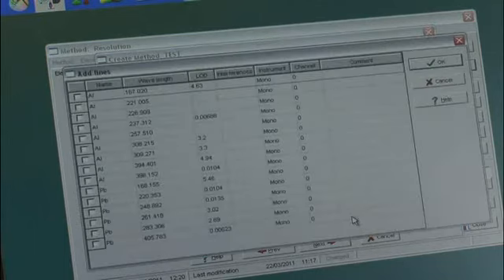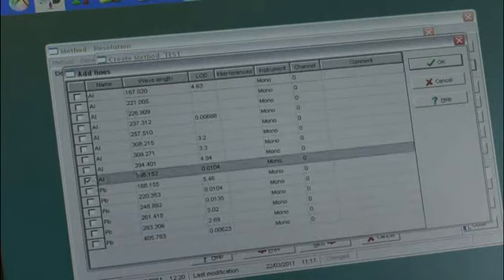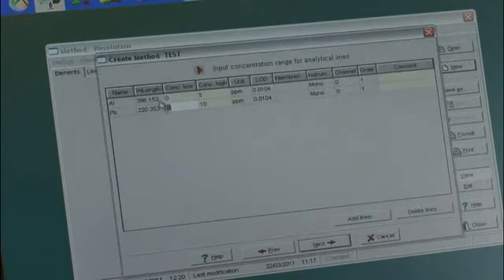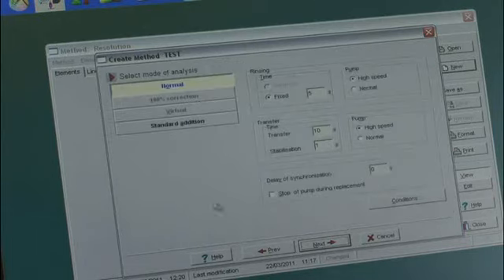And then I want to add a line. So here it'll pull up the most popular aluminum and lead line. So I'll choose the 396, which is what I used. So now we have these two elements, or these two wavelengths in our method. Go to next. And here, the pump you don't have any control over, so it doesn't matter what this is on. Transfer time is the amount of time it's going to take from your sample to get to the plasma. So if I say 10 seconds, it's going to wait 10 seconds. Rinse time is mainly for an auto sampler, so when it leaves the sample, it'll go to a rinse position and back to the sample again.